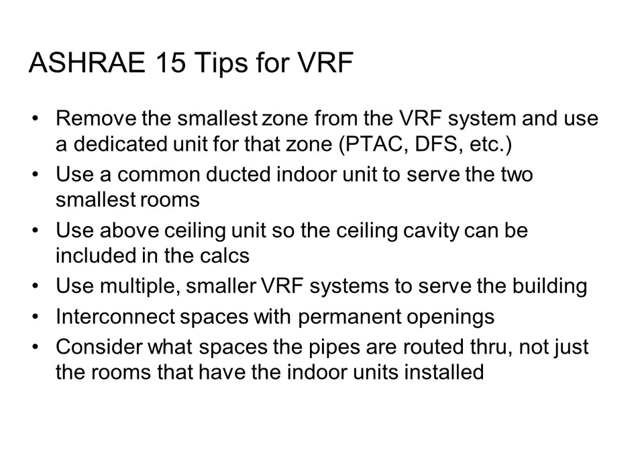Now, for a VRF system, that's not very practical because I have so many zones to think about. But for a chiller room, a mechanical room, that makes a ton of sense, right? Because it's all in one room, I only have to buy one sensor. But for a VRF distributed system, it doesn't make sense. But yes, Andrew, those limits are for all spaces, including the mechanical room.